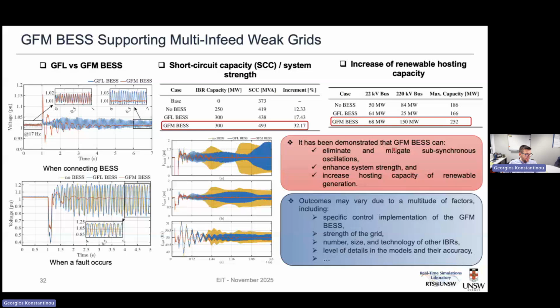So we see that the inclusion of grid forming converters in very weak grids gives us these benefits because we are able to eliminate oscillations that might exist or that we might be at risk of experiencing. They enhance system strength and they also increase hosting capacity of renewable generation. And these are very interesting conclusions because we do expect to see more weakness in networks. Australia is experiencing that already. We probably will start seeing it around the world in different areas. Some might take a while, some might be very far away. But in some parts of the world, these are things that we need to consider sooner or later.